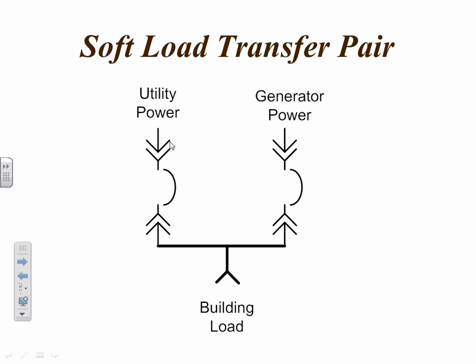At that time, they bring power back to this point. Same thing happens. Sensors in here look at the generator power versus what the utility is doing now. It synchronizes, matches speed and voltage, and closes the utility breaker. Load is ramped off the generator back onto the utility. The load still doesn't know anything happened. It hasn't seen an outage. So it's a user-friendly piece because IT people aren't screaming, hey, we lost power, because they've not seen an outage. So it's a really sophisticated way to transfer power and also help out the utility.